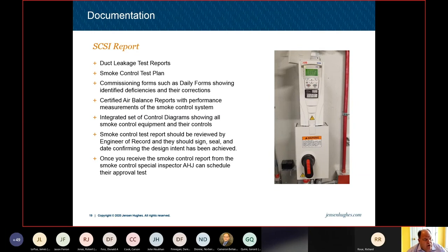That smoke control test report needs to be reviewed by the engineer of record, so that the mechanical from the MEP firm typically is the one doing that, and they're required to sign, seal, and date confirming the design intent has been achieved. And then once you have that smoke control report from the smoke control special inspector, that's provided to the authority having jurisdiction, and that's normally when that test is scheduled, to perform the smoke control test with the authority having jurisdiction.